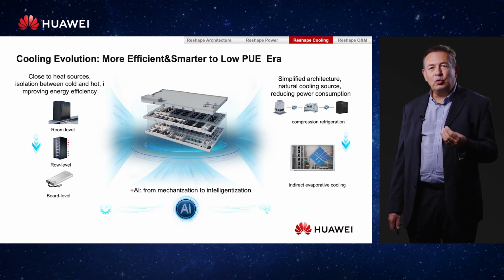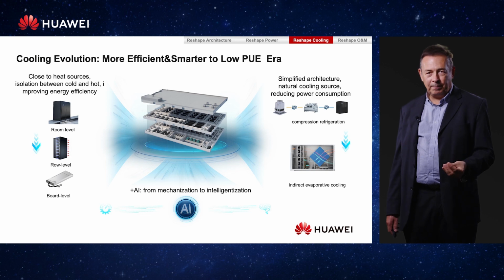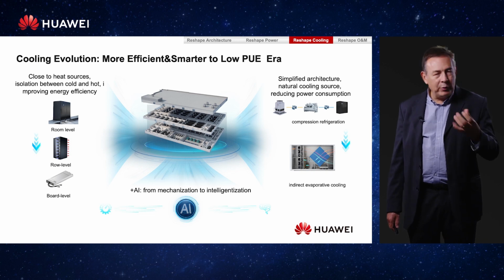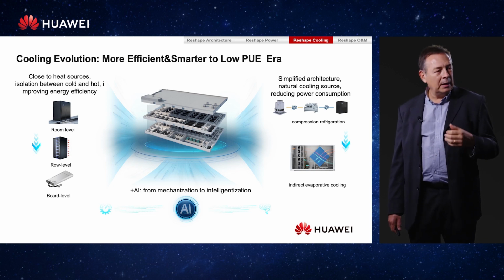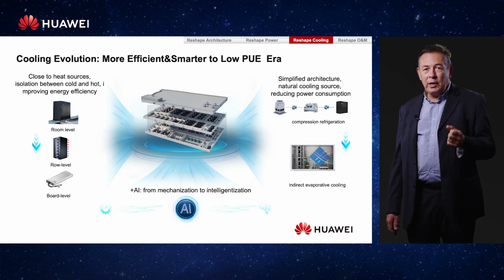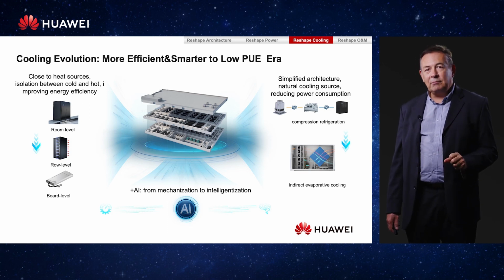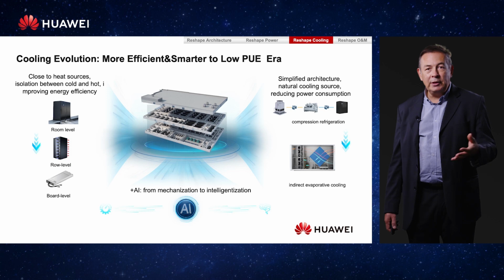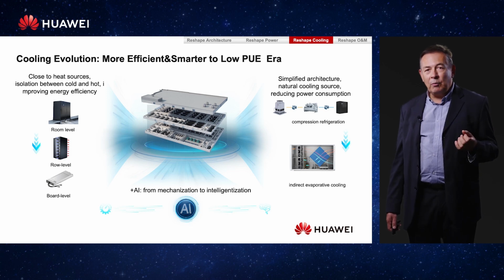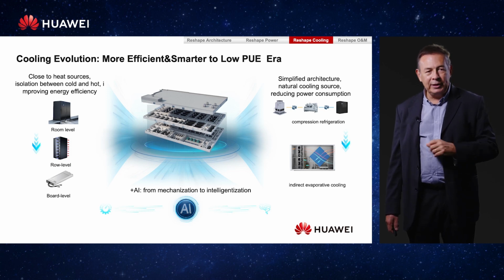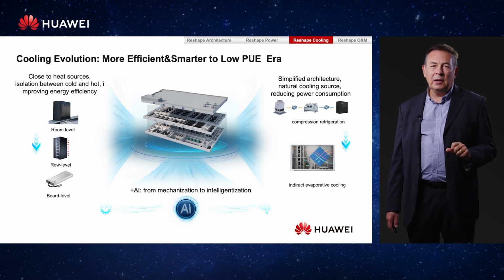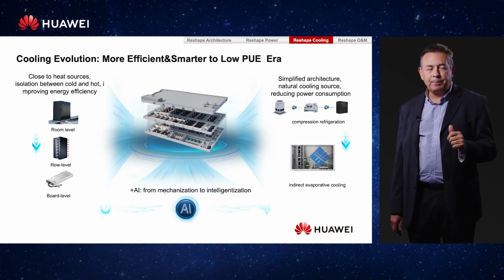The idea is to cool the devices as close as possible. For example, you can have liquid cooling at board level, in-row cooling close to the IT racks, and also in-room cooling. We need all these systems to be as efficient as possible, so we need to simplify the architecture and use natural cooling as much as possible, to reduce power consumption and become greener.